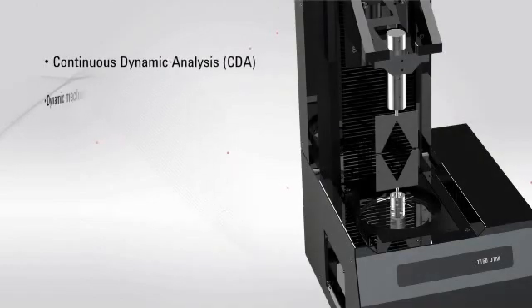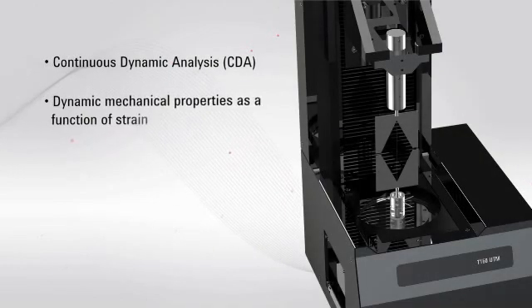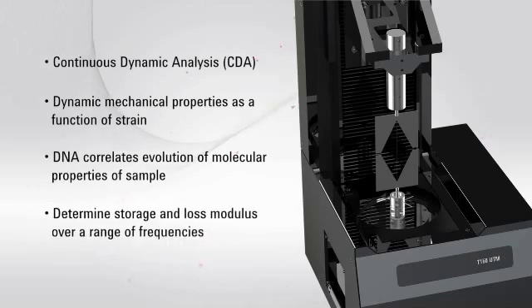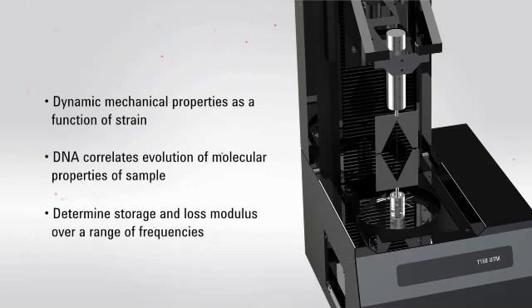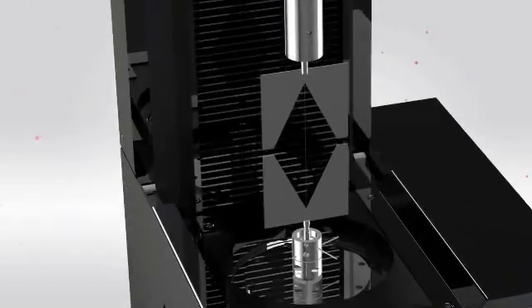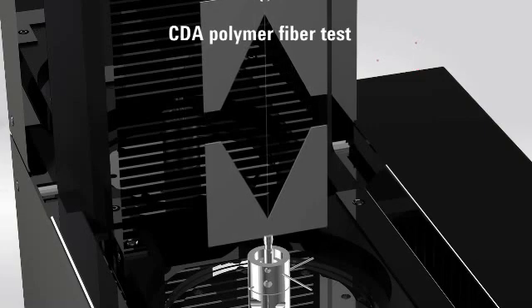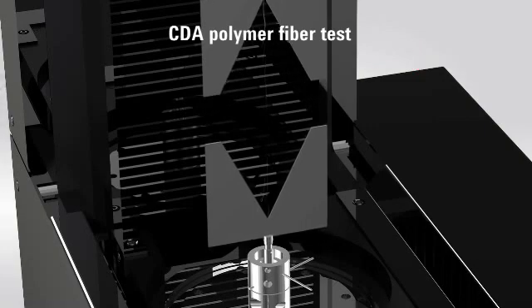Keysight's Continuous Dynamic Analysis Mode, or CDA, allows the continuous measurement of dynamic modulus as a function of strain. This type of operation, which is unique to the Keysight T150, enables users to measure mechanical properties of time-dependent and viscoelastic materials continuously as the material is strained. As seen in the illustration, CDA works by superimposing a sinusoidal oscillation on the load cell while pulling the sample with the crosshead.